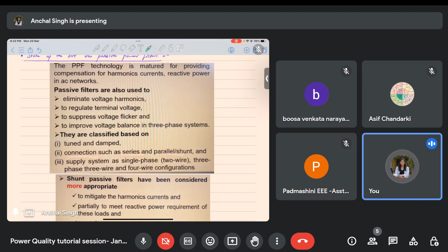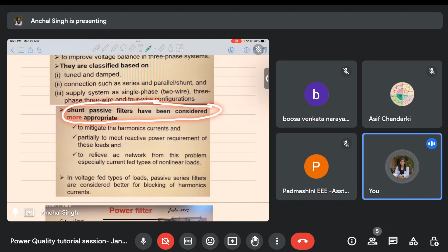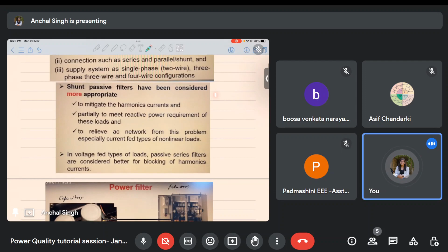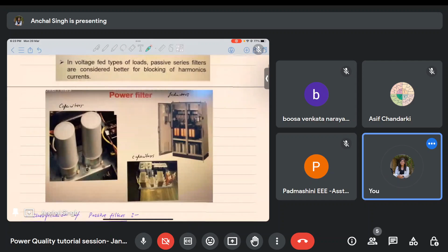Shunt passive filters have been considered more appropriate to mitigate harmonic currents. We know that the major dominant power quality problem is current and harmonics in the current. So the most important area of application of these passive filters is in shunt, for harmonic compensation of currents and partially to meet the reactive power requirement of these loads. That means for power factor correction, to relieve the AC network from the problem, especially current fed type of nonlinear loads. So these are for current fed type of loads, and for voltage fed type of loads, series type of filters are considered better. These are just a few examples of power filters.